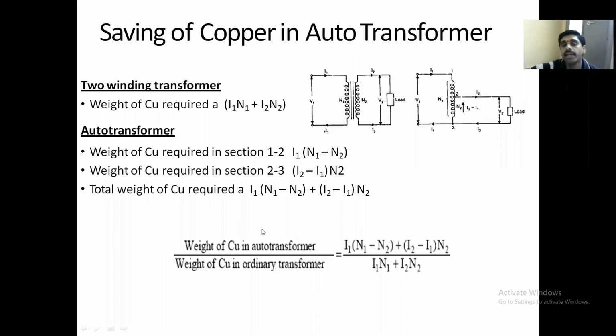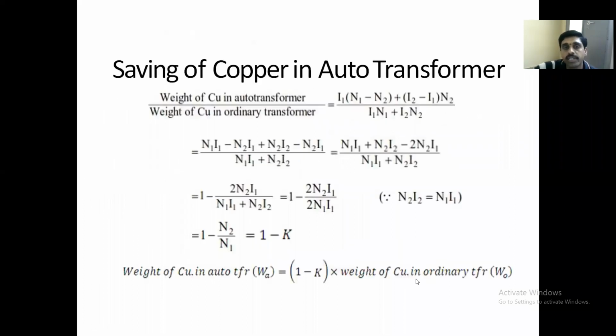So therefore, the weight of the copper in the auto transformer divided by the weight of the copper in the ordinary transformer, this is the ratio you can write. You can observe from this expression which is more. If you continue these expressions, simplifying them and using N2 I2 equal to N1 I1, we get this ratio equal to 1 minus N2 by N1, that is equal to 1 minus K. Means the weight of the copper in the auto transformer is 1 minus K times the weight of the copper in the ordinary transformer.